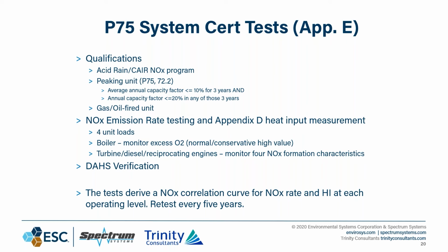It's a healthy list. And perform a DAHS verification, prove your equations work. The tests derive a NOx correlation curve for your NOx rate and heat input at each operating level. And assuming that you abide by the rules under Appendix E, you only have to retest every 5 years.